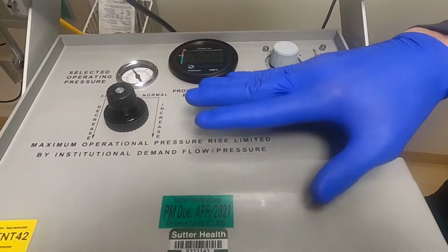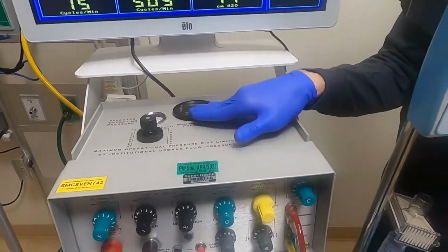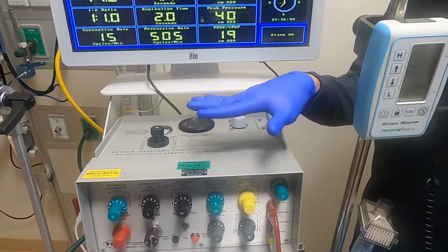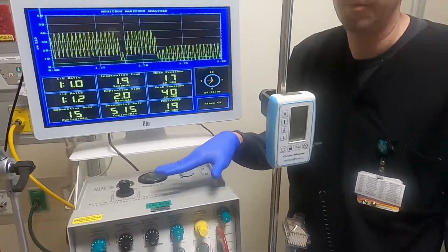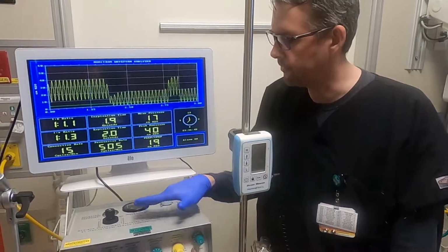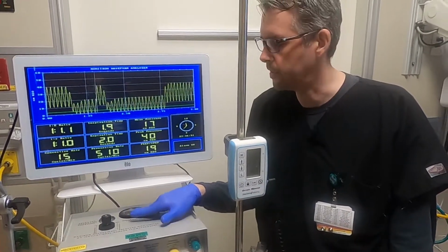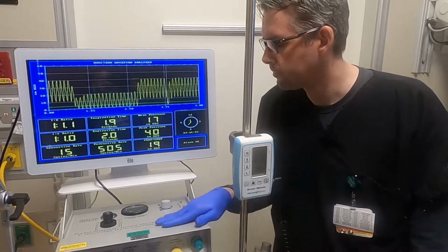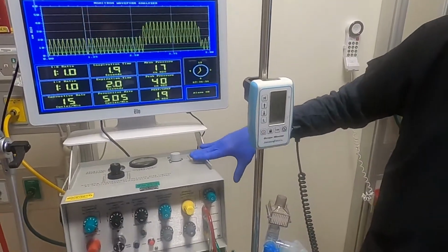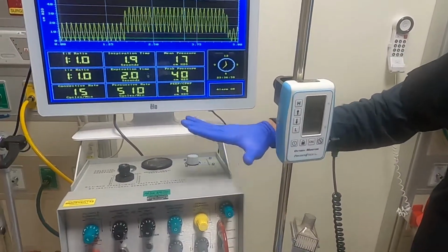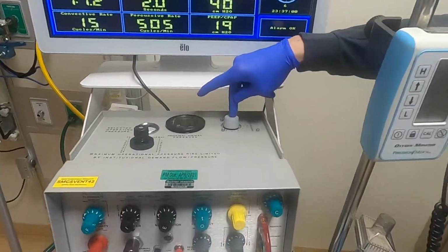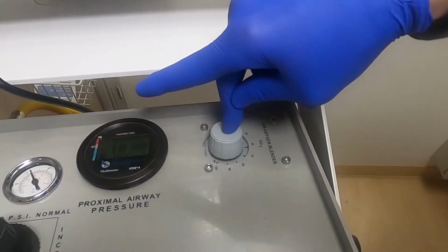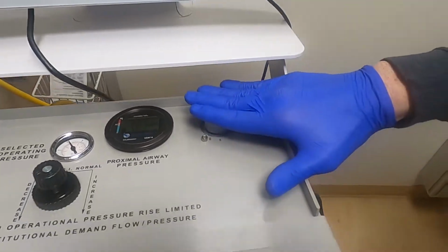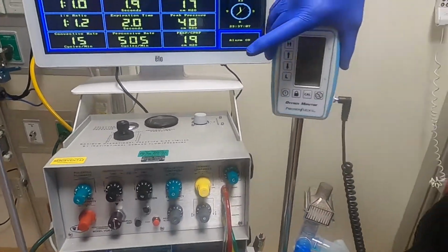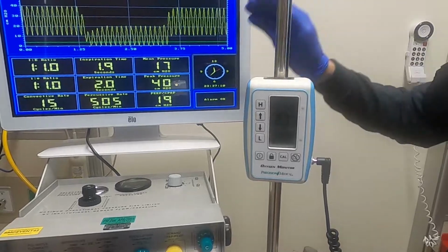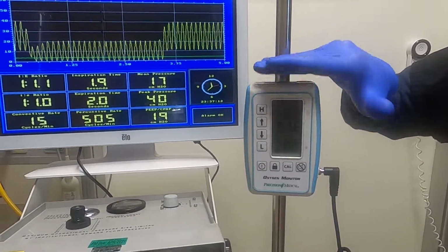When the doctor orders settings for this ventilator, this is where they're going to be set. So if they want to have 30/10 and a rate of 500, you're going to set the ventilator so that's where it's going to read 30/10 and a rate of 500. Over here is your oxygen analyzer, or your blender. This is where you're going to set your FiO2. And in addition to this, we have our oxygen analyzer here, just to make sure that it's easy to see what kind of FiO2 you're on.